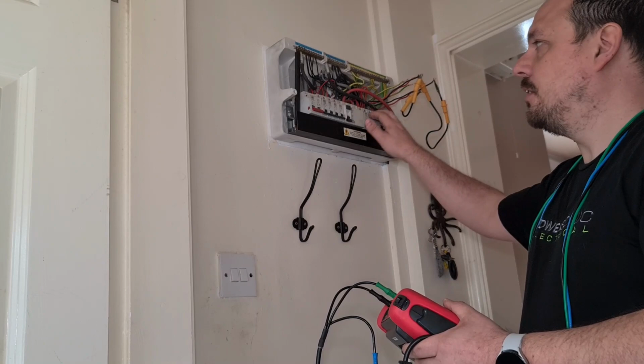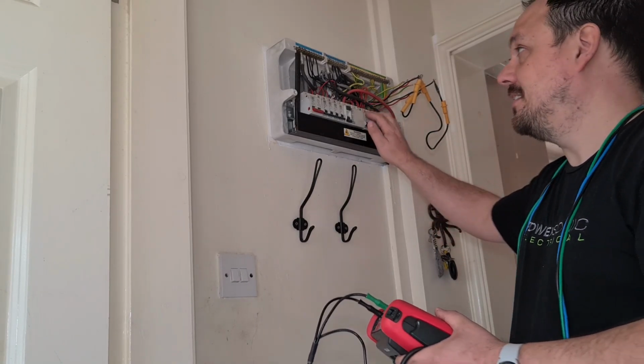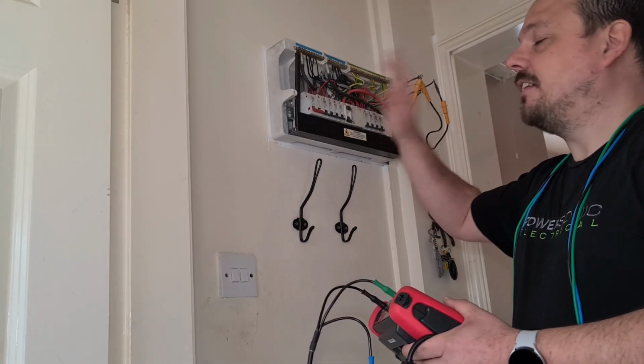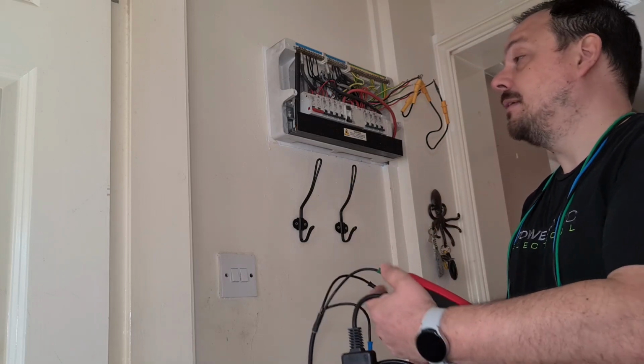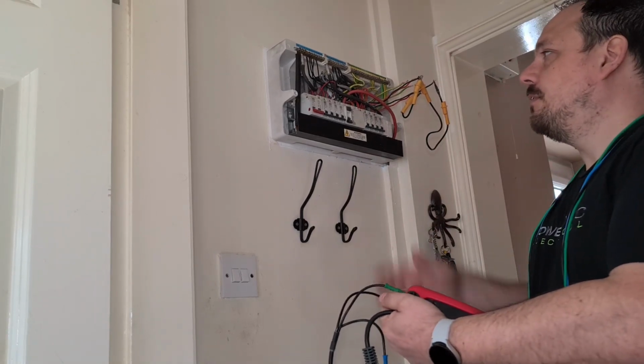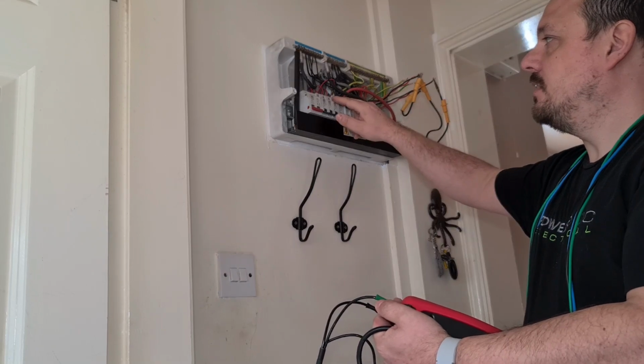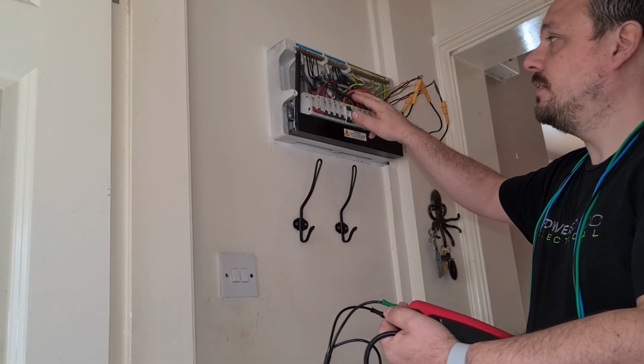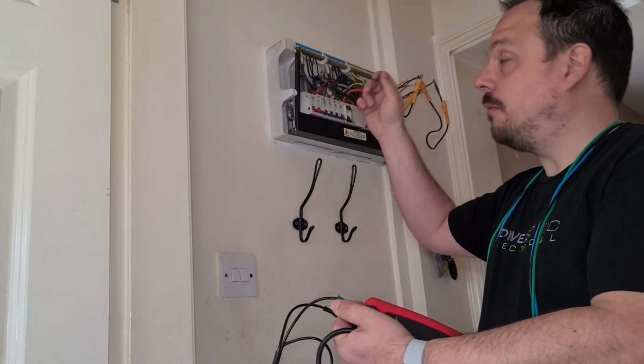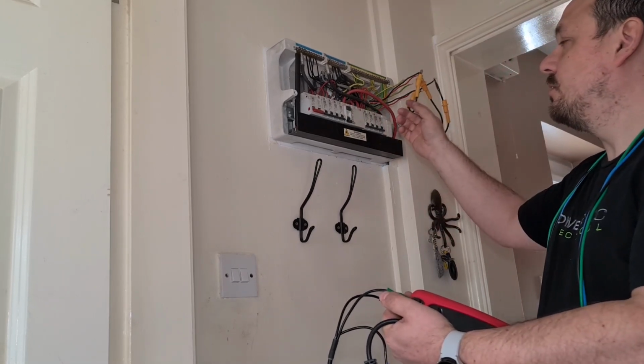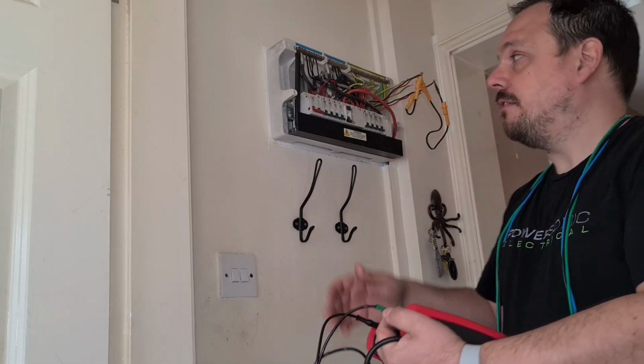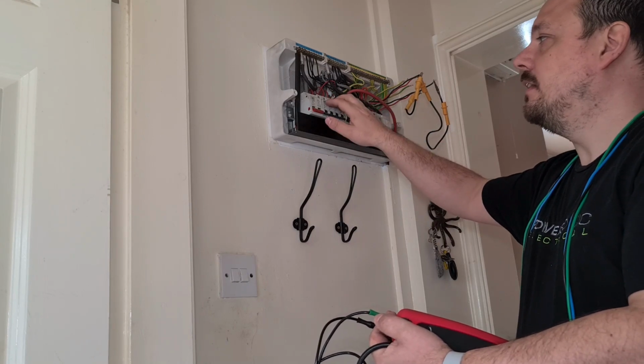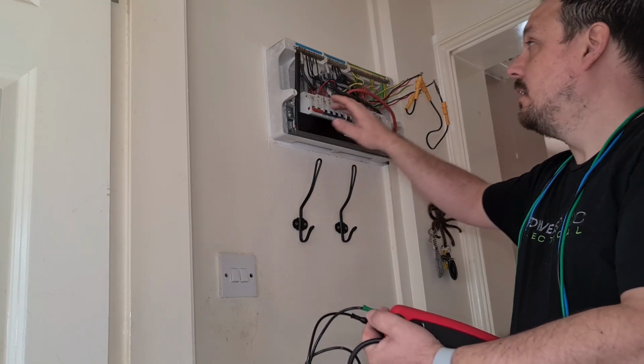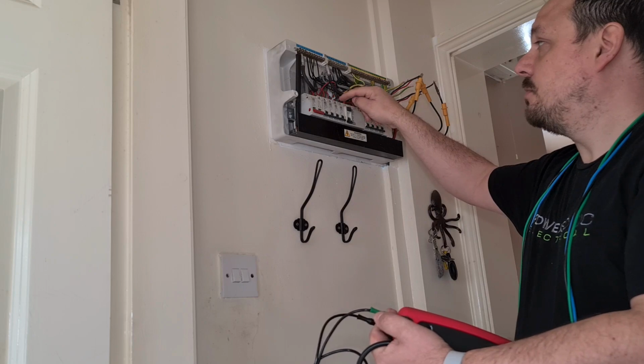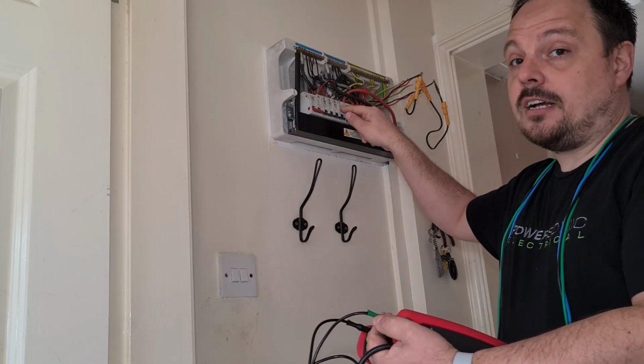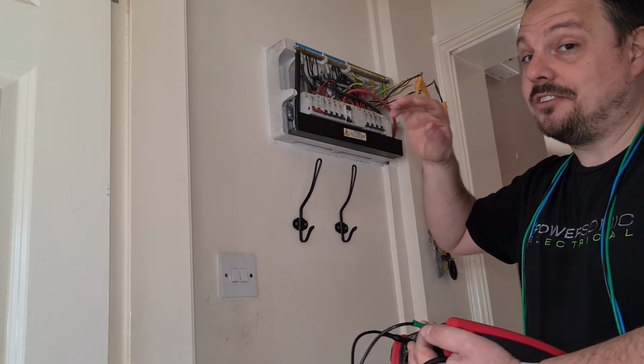So obviously I'm going to run through the dead tests on the rest of these socket circuits now, and the lighting circuits, and when I say dead tests I mean the continuity tests. With the lights, you can join your CPCs into your lines if you want, and this is the way I tend to do it, is take them out and pop them into a little Wago, or use some crocodile clips, just so you're outside of any of the terminals within the consumer unit itself. Some people would take the CPC and just pop it into the top of the MCB with the line. Perfectly acceptable way of doing that, obviously, as long as the power's off.